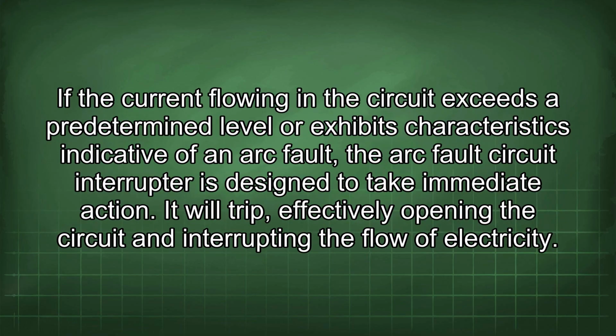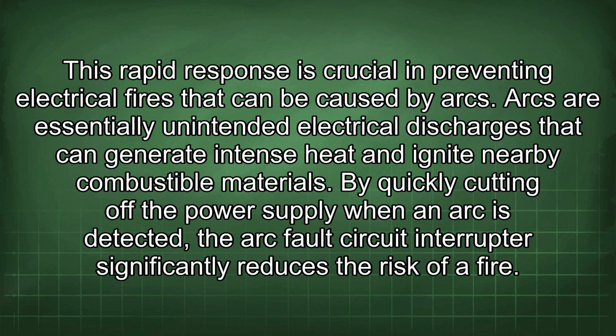If the current flowing in the circuit exceeds a predetermined level or exhibits characteristics indicative of an arc fault, the arc fault circuit interrupter is designed to take immediate action. It will trip, effectively opening the circuit and interrupting the flow of electricity. This rapid response is crucial in preventing electrical fires that can be caused by arcs. Arcs are essentially unintended electrical discharges that can generate intense heat and ignite nearby combustible materials. By quickly cutting off the power supply when an arc is detected, the arc fault circuit interrupter significantly reduces the risk of a fire.